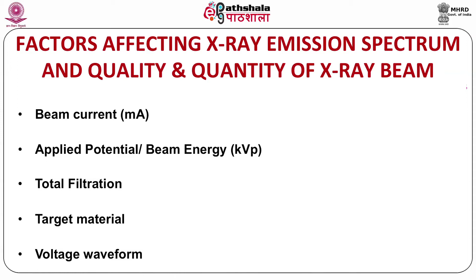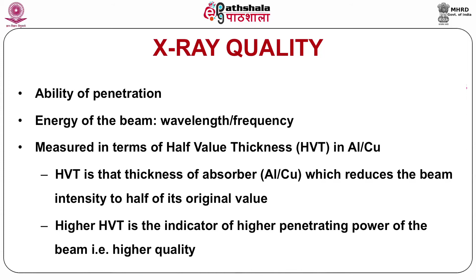However, peak kilovoltage alone is not a good indicator of the penetration power of the X-ray beam. Hence, X-ray beam quality is measured and specified in terms of half value thickness in aluminum or copper. HVT is defined as that thickness of absorber, that is aluminum or copper, which reduces the beam intensity to half of its original value. Higher HVT is the indicator of higher penetration power of the beam, and the beam is called a higher quality X-ray beam.